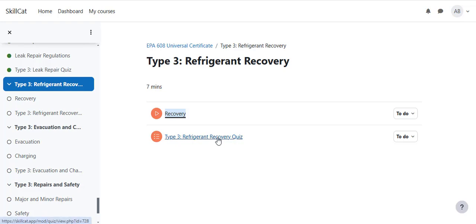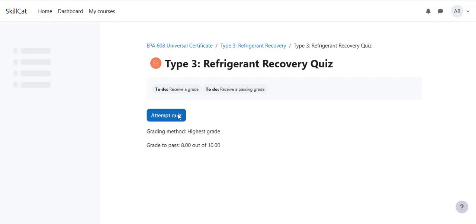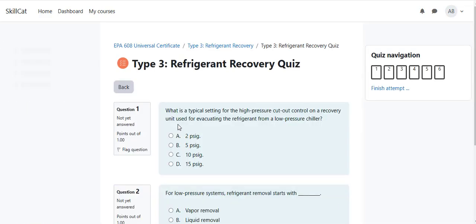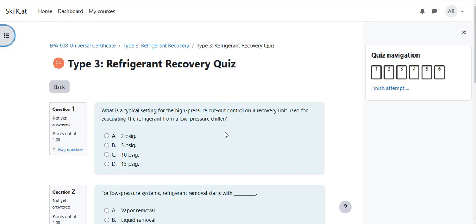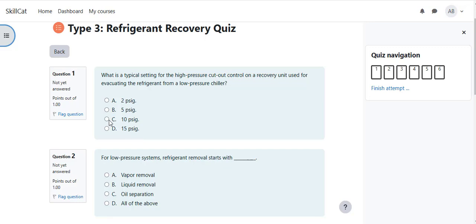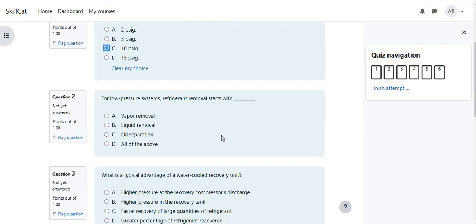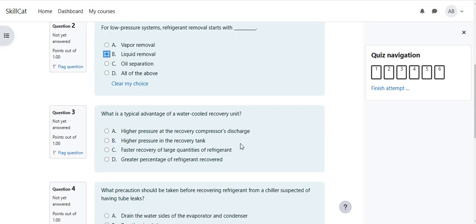Okay, let's go to refrigerant recovery quiz. We have now here 6 questions. What is the typical settings for the high pressure cut out control on recovery unit used for evacuating the refrigerant from low pressure chiller? It will be 10 psig. For low pressure system, refrigerant removal started with liquid removal. What is the typical advantage of water-cooled recovery unit? Higher pressure as the recovery compressor discharge, higher pressure in the recovery tank, faster recovery of larger quantity.